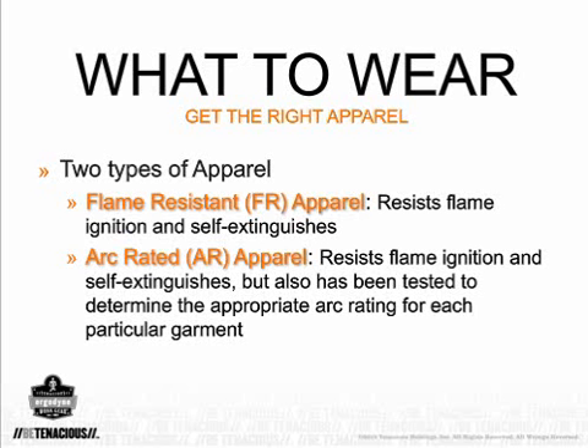So how do you select the proper apparel for your employees? Let's begin by understanding the two different types of apparel. Flame-resistant apparel resists flame ignition and self-extinguishes. Arc-rated apparel also resists flame ignition and self-extinguishes, but we can take it one step further because arc-rated garments have been tested and a rating has been applied to that garment.